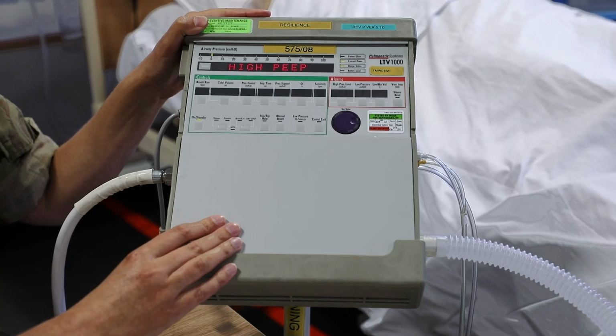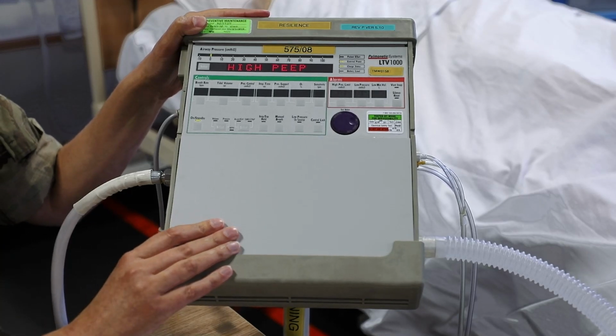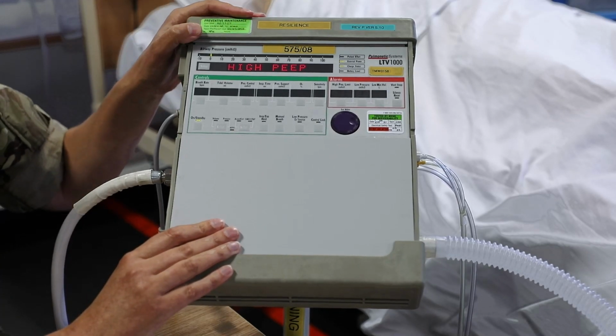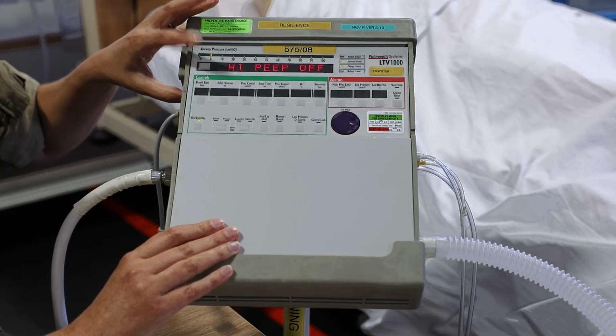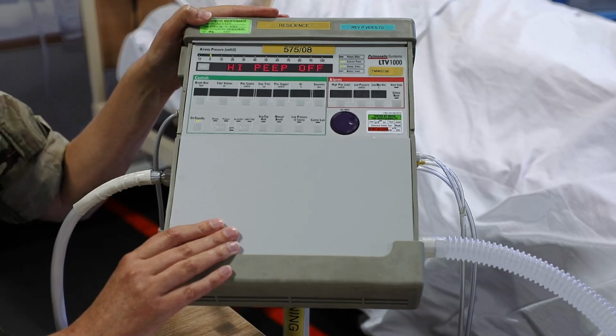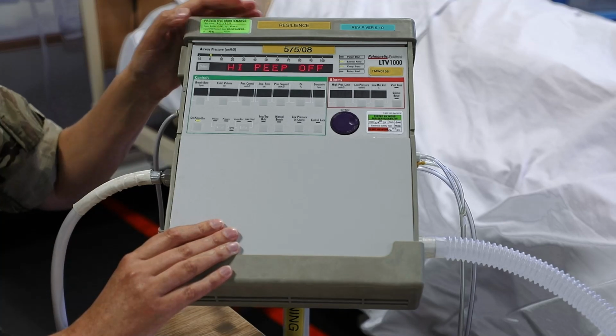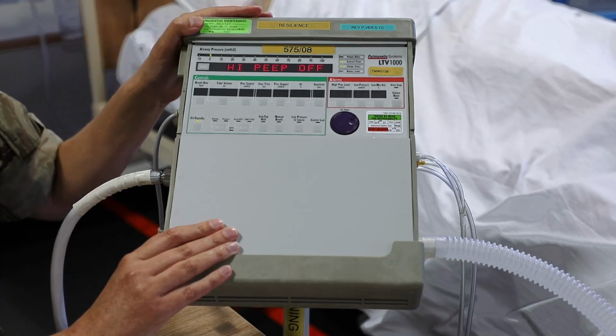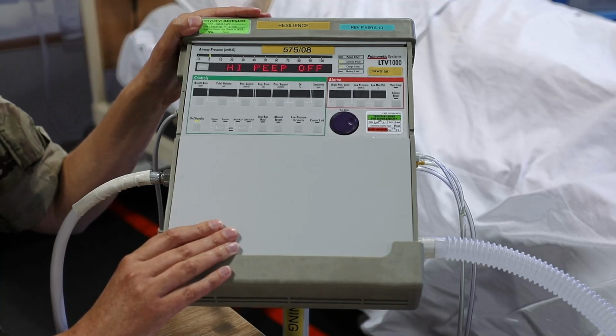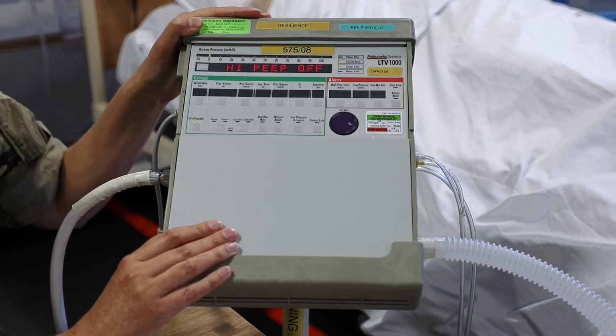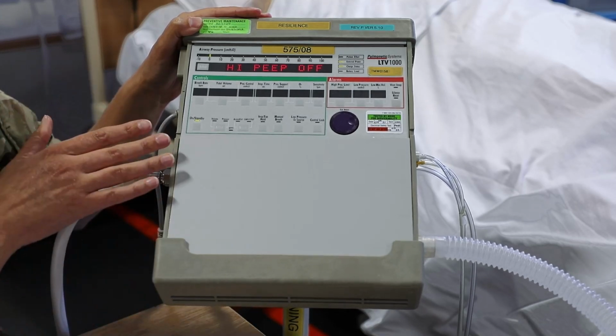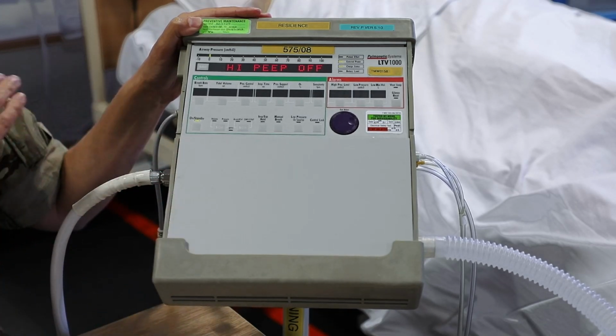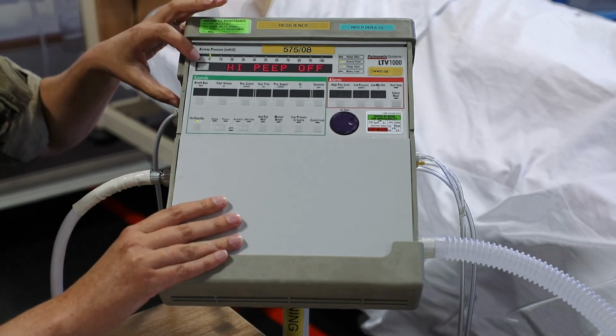Next option here is the high PEEP alarm. We would recommend that you have this switched to off. So if we press select, currently it's set off. And the reason for that is that it prompts you to set a high PEEP alarm once you've started ventilating the patient. So start off with it off, and then the LTV will remind you that that is currently set off.